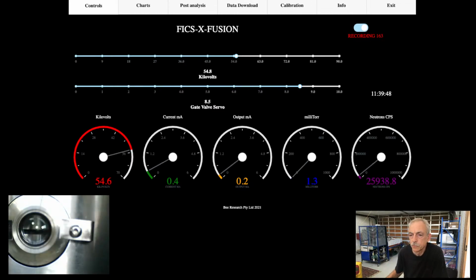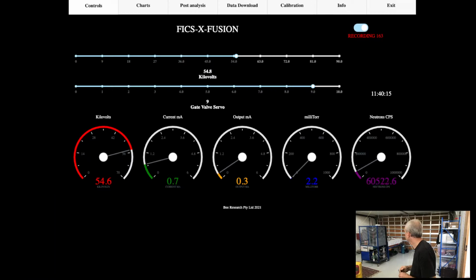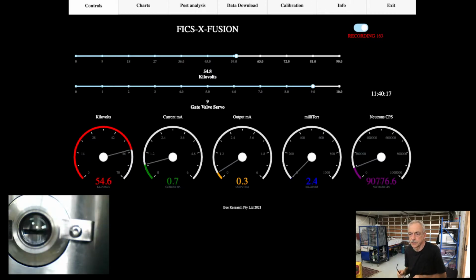Okay, so we're running at the moment. The reactor is running. I can't see any plasma in the viewport, so it's running at a pretty low kind of current and pressure, but it is running. If I can possibly ramp it up a little bit, as long as we don't get that total breakdown, that's what we want. Okay, so here we've got a bit more current, and that should bring up the neutron count. But I'm also getting a significant amount of arcing, and this is going to bring down the electronics, I think.